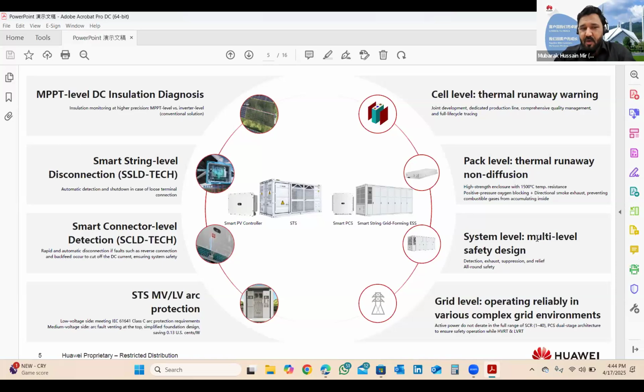There is also smart string disconnection level, SSLD technology available. If any fault occurs in any string at a distance of more than 200 or 300 meters, this function can detect those problems into the strings and disconnect the inverter. In the long term, this stops the solar power plant from fire burning, not only on the inverter side but also saves the plant from any big losses.